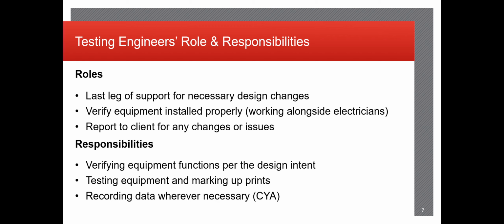Testing all the equipment, all the circuits, everything, and marking up the prints is extremely important. This shows that if something does go wrong or something needs to be changed on the prints, we mark it up, make a note of it, and then those will be sent back to the design engineers at the end of the project for them to pretty much redraw whatever we mark up and submit those to the client as what we call as-builts, which are pretty much the final design of the print that shows what equipment is in service and how it should look if someone were to go out on site and utilize those prints.